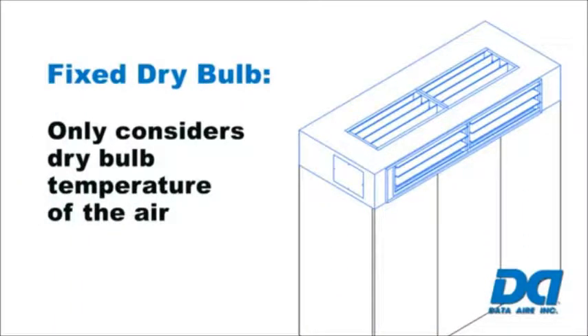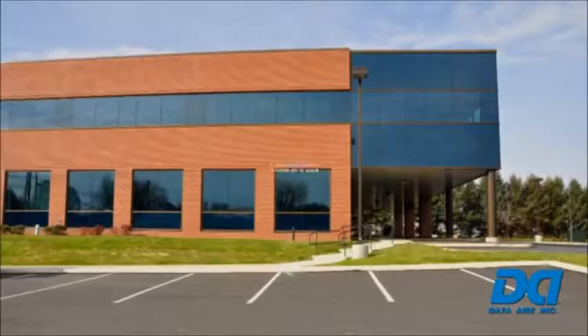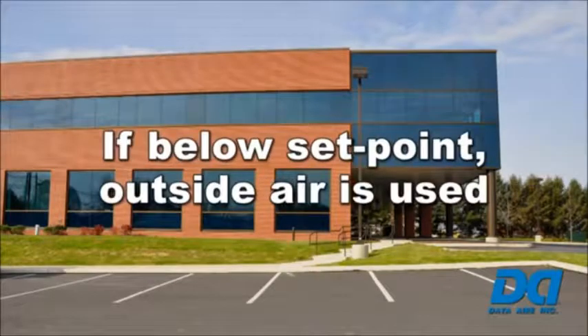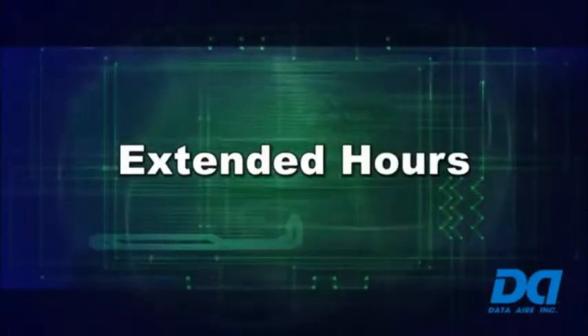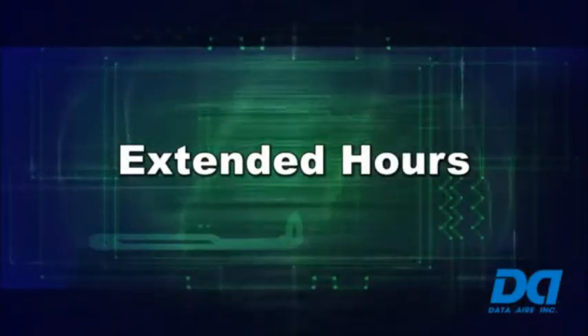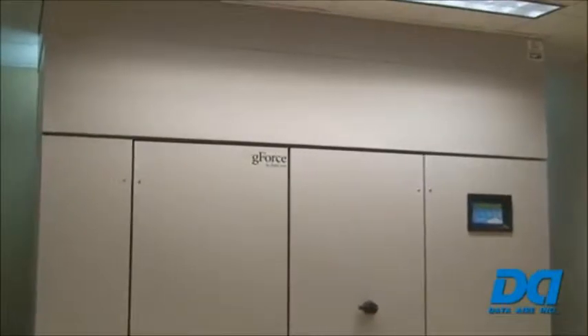The fixed dry bulb method only considers the dry bulb temperature of the air. If the outside air dry bulb temperature is below the set point, outside air will be used. Data Aire's control logic permits extended hours of economizer use compared to many competitive units available in the market today.